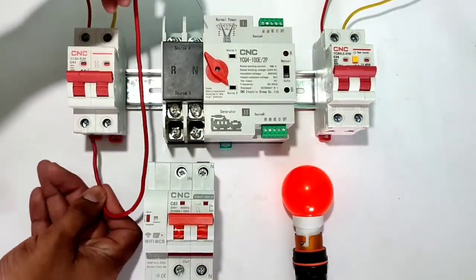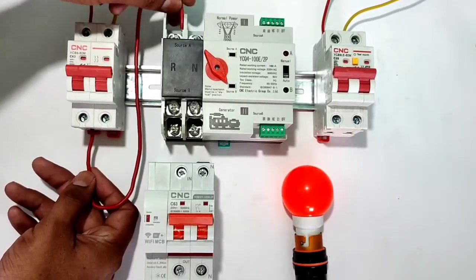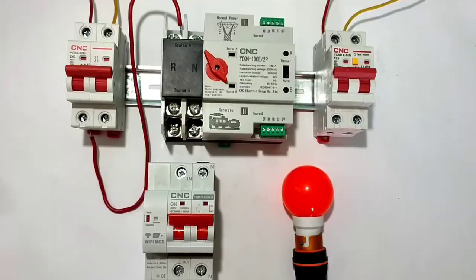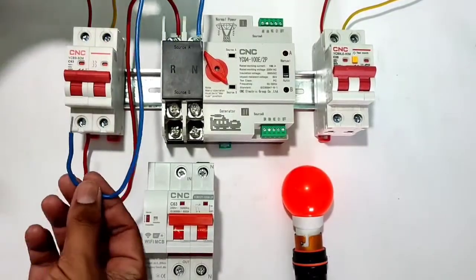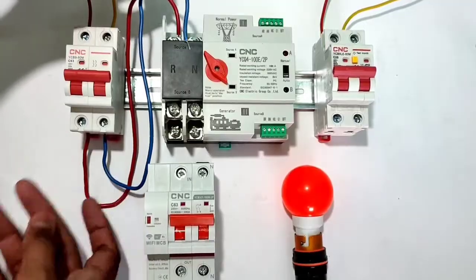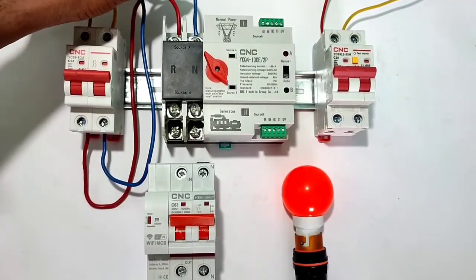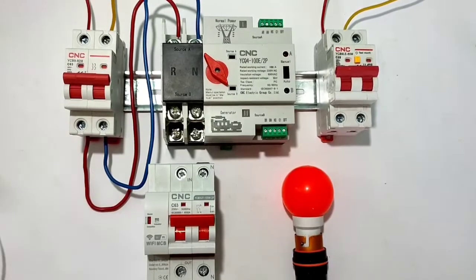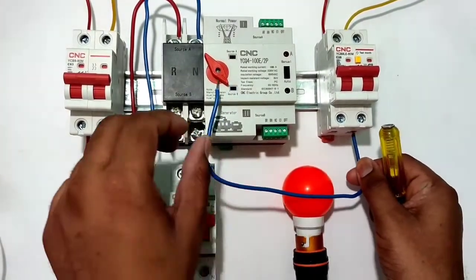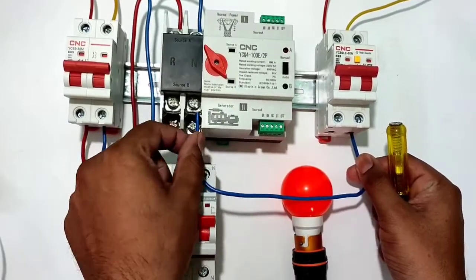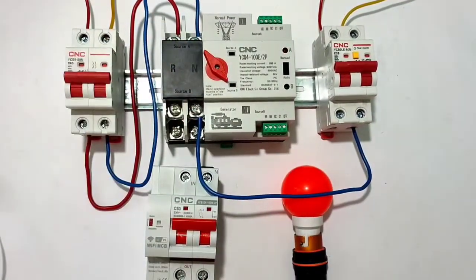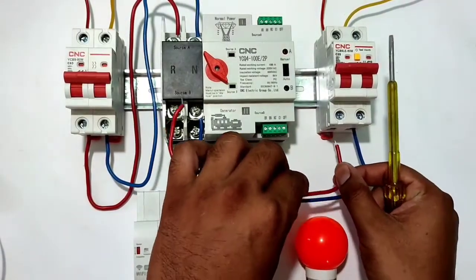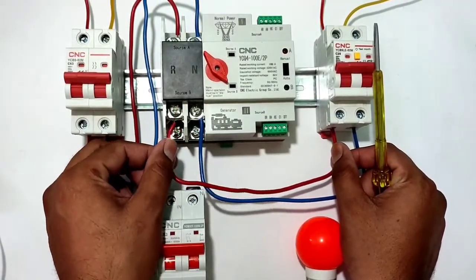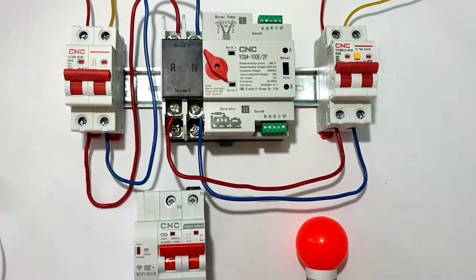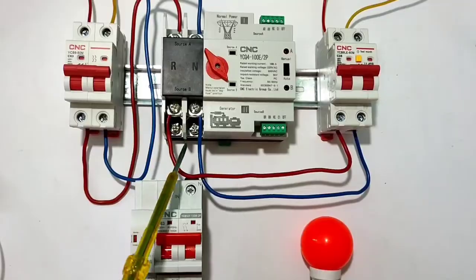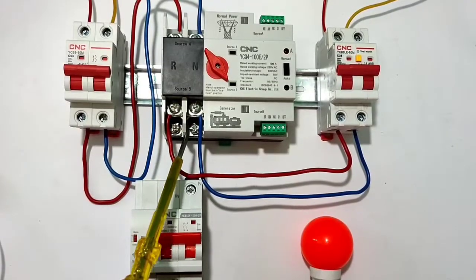Now for the output power supply, we connect a phase wire from the first circuit breaker to the normal power supply source A R terminal here, and the neutral connection to the source A neutral terminal. Okay, it's a very simple connection. Now the same connection for the secondary source, which could be a generator. So we connect a neutral wire here to this source B N terminal. Now we connect the phase wire. So we connect one connector from the MCB phase to the source B R terminal. Okay, so our input power supply connection is now done in this automatic changeover switch.